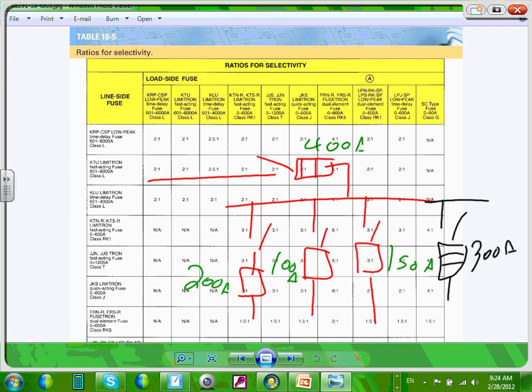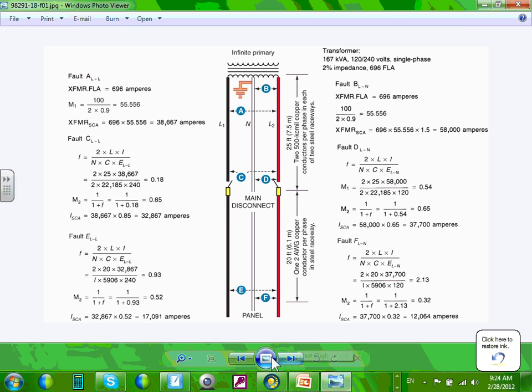If you do it this way, guys, you're almost guaranteed full coordination, especially with fuses and almost with circuit breakers. So that's what this ratio for coordination gives you. Most of it is 2. Can you guys see 2, sometimes 2.5 here, but for the most part, here's a 3, based on the type of fuse that you're trying to coordinate. There's a couple of threes here. But for the most part, if you can continue with a 2-to-1 ratio between the main and the feeder, you're almost guaranteed coordination without doing any study. Okay, so that's basically what I wanted to show.